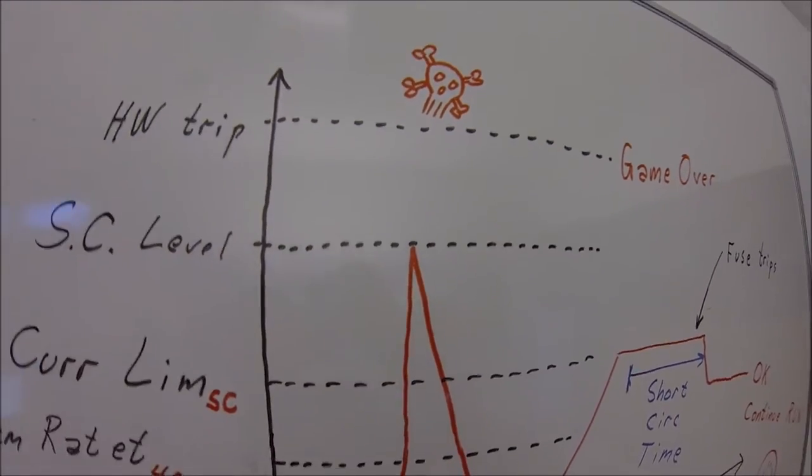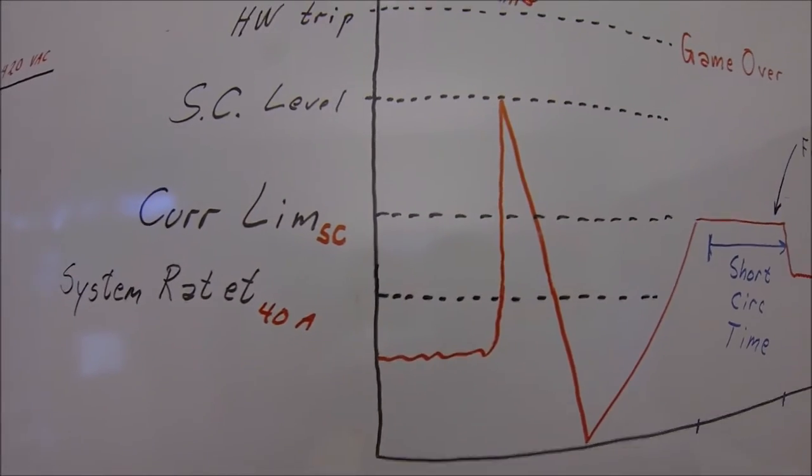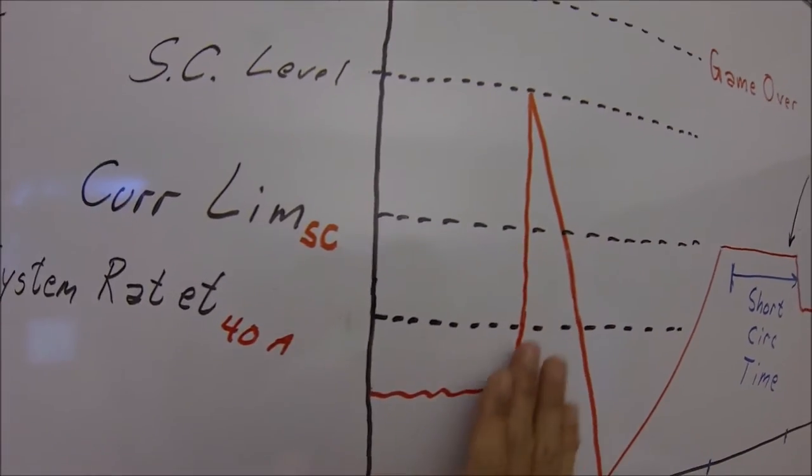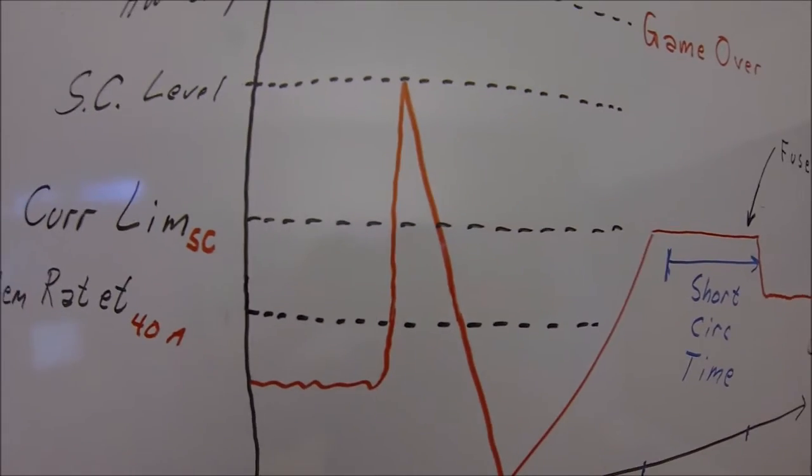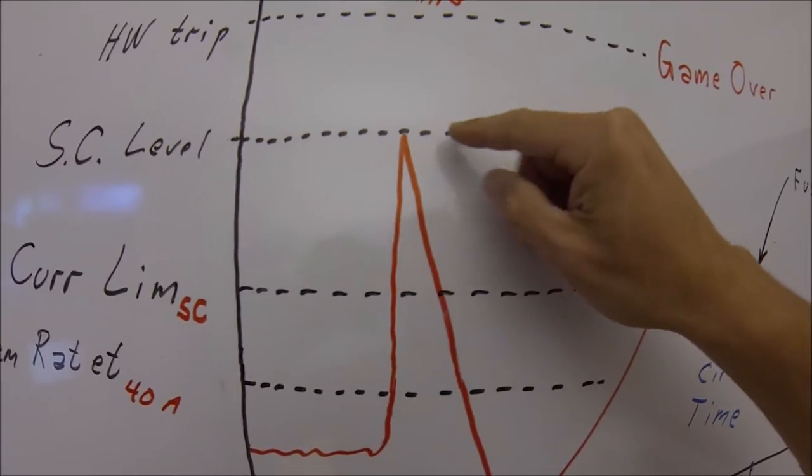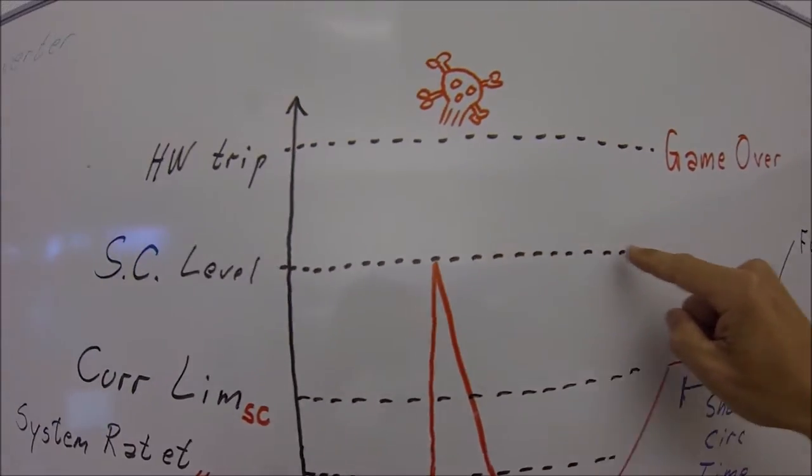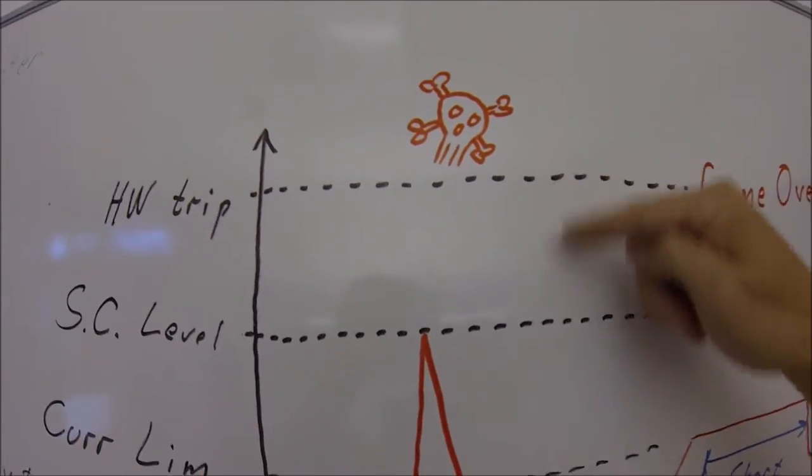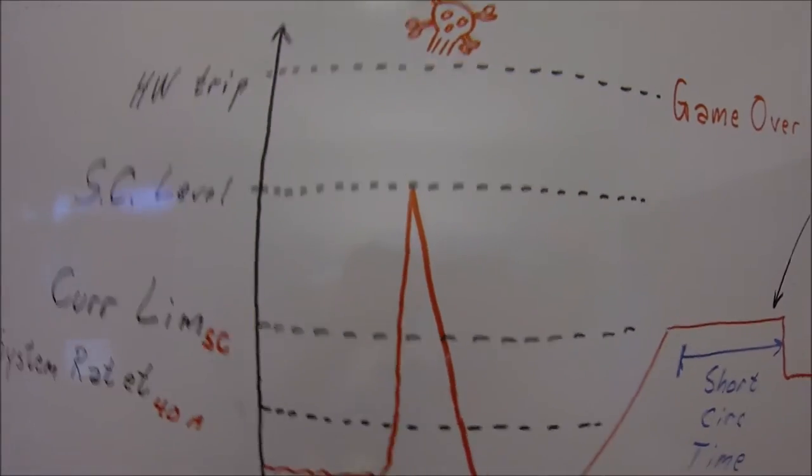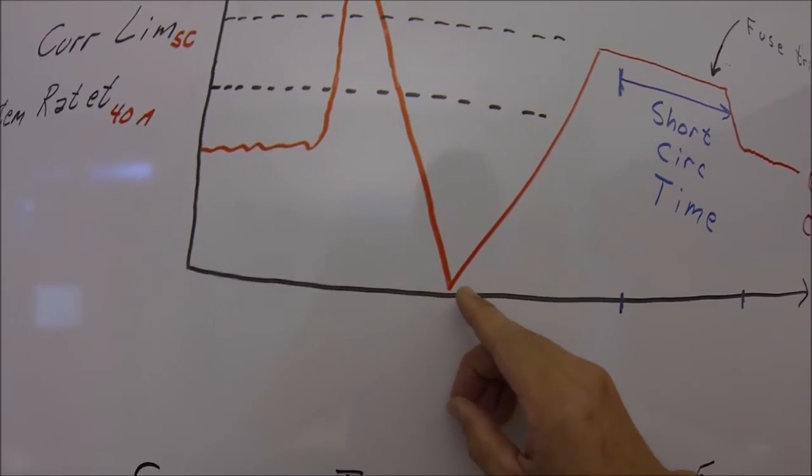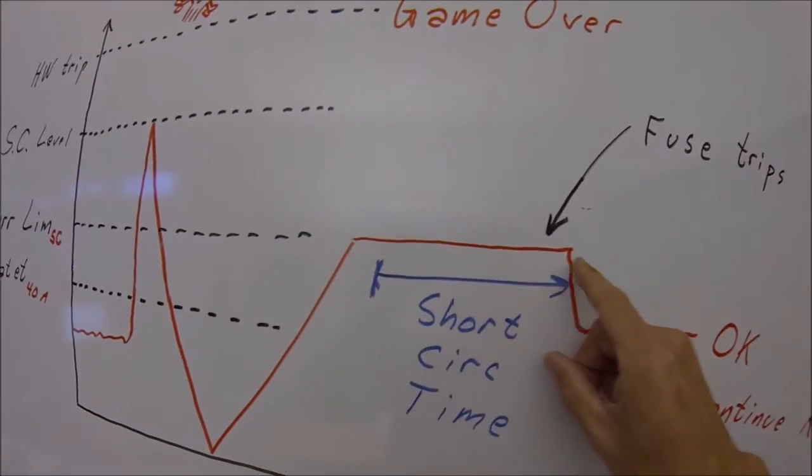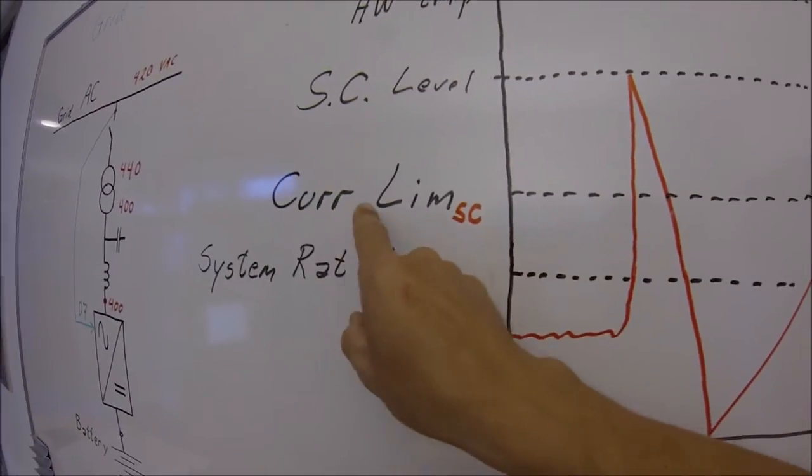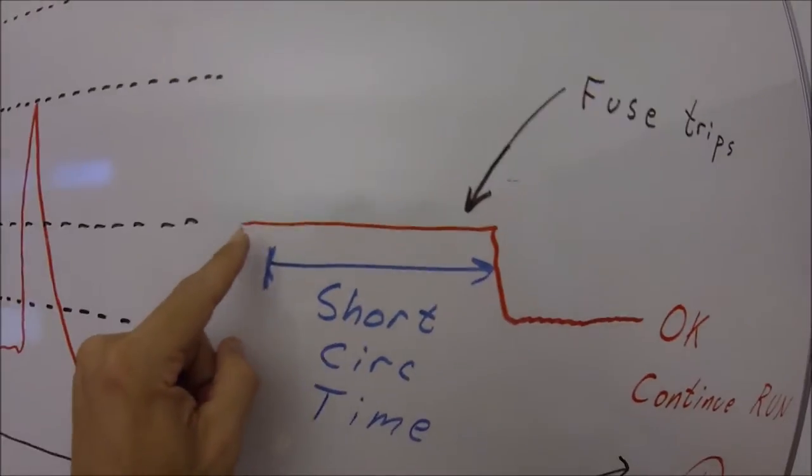Well we have a functionality in our drive which detects the short circuit. The very rapid rise of current will be detected and what happens, it cuts off the control system for the IGBTs. It just cuts off the current and this happens at a certain decided level. We can decide what level this should happen and it should be with a safety margin to the hardware trip of course. The current will drop to zero, then a current controller will take the current up to a decided level here.